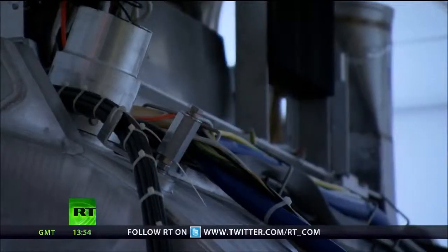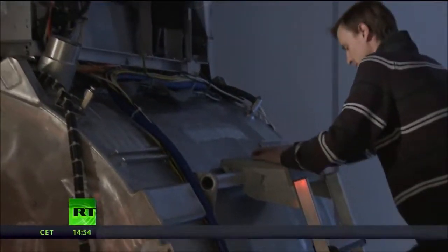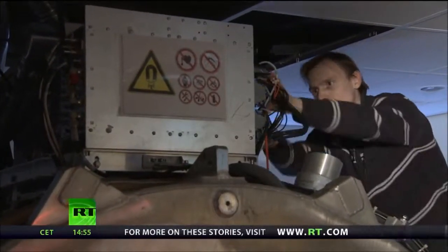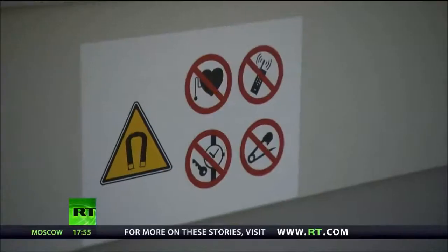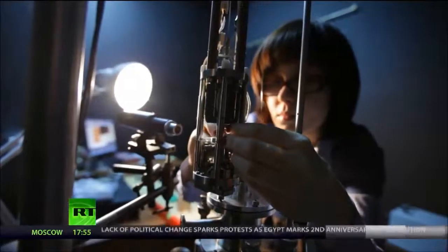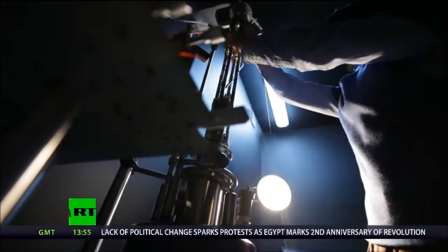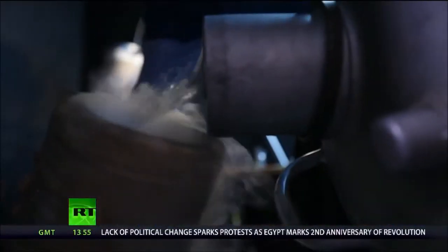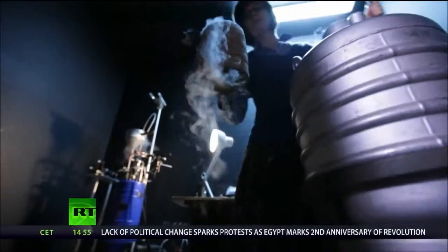Such a construction has numerous advantages. First among them are economic. For one thing, by cutting pricey helium out of the equation, or at least significantly reducing it, these imagers are much cheaper to produce and operate. In Russia, the liquefied gas costs around $25 per liter, which adds $75,000 to $100,000 to the initial price tag.